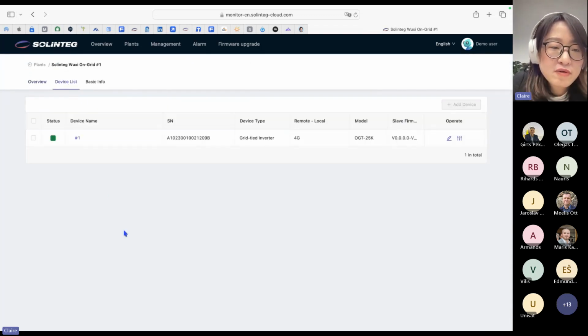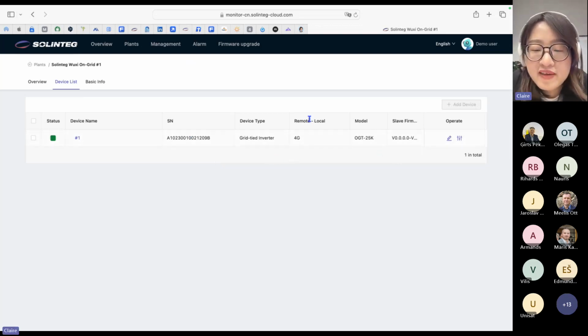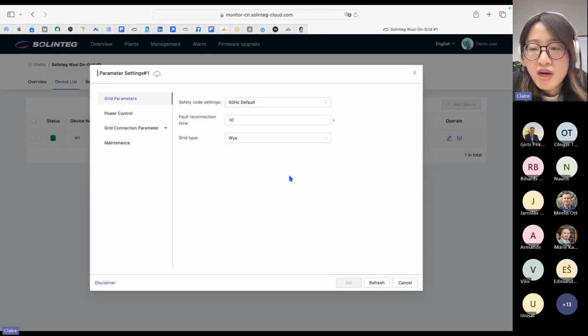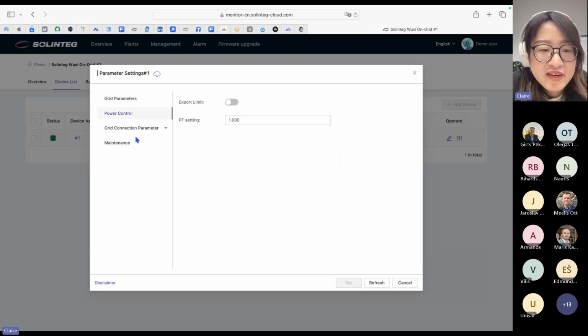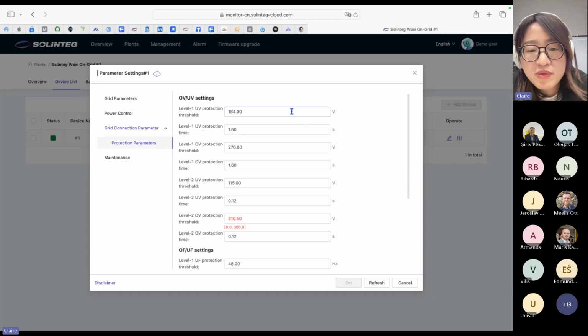And this is a device list, so we can see in this plant, we only have one device connected, and this is the device serial number, and the device uses a 4G connection. The device reports the power and firmware information. And here we can do some remote parameter modification of the device, like the safety code, the fault reconnection time, the grid type. Also, the power limitation can be set here, and the protection parameters.